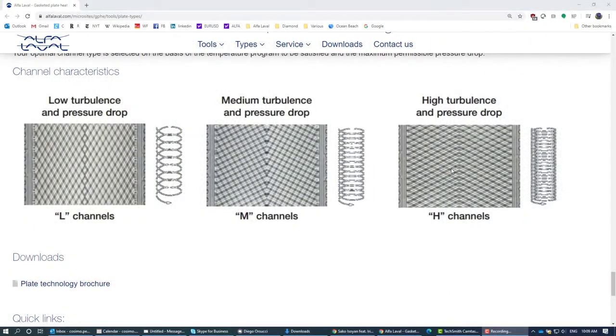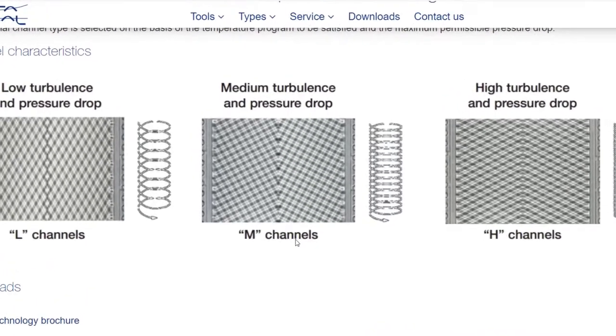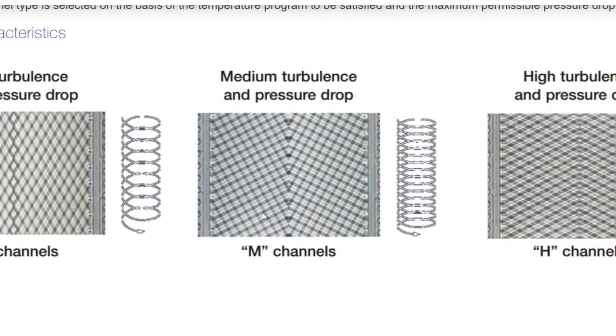The higher number of contact points forces the fluid to take a much harder path through the channel. This causes more turbulence and shear stress. Both promote higher heat transfer, but it comes at the cost of pressure drop. Of course, you can mix the types and come to a number of contact points between the high and the low extremes.